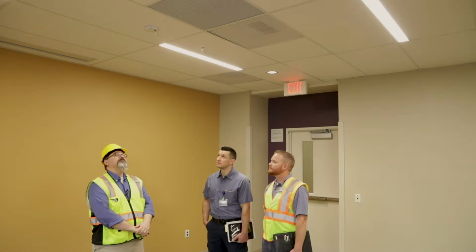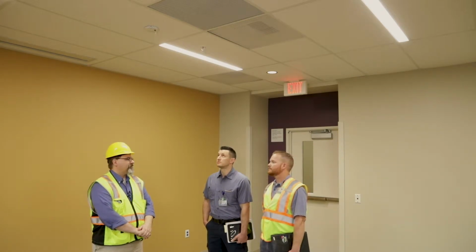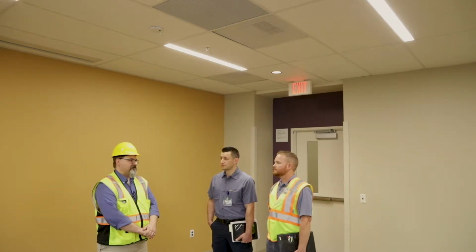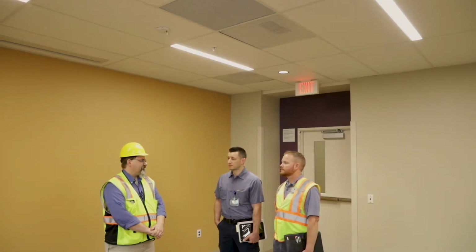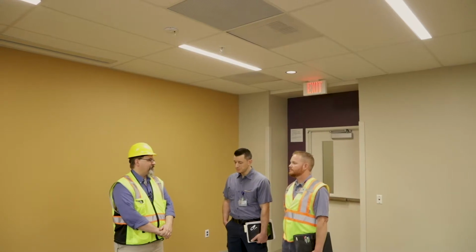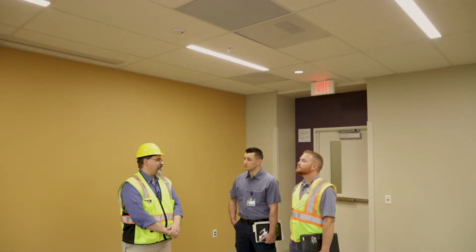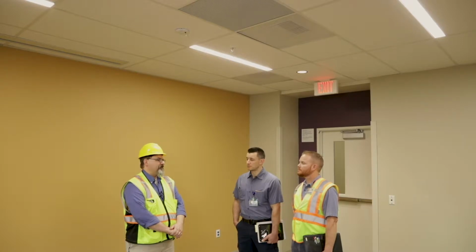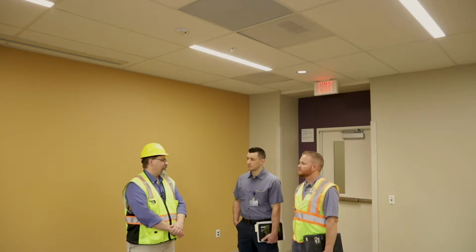So we're back to the sensors here. Most of the sensors in the building have been programmed to be manual on, so you have to go to the switch to turn your lights on. With the exception of bathrooms, we wanted those to be auto on, so when you walk into a bathroom, the light's on. If you're sitting in the bathroom and the lights go off after 20 minutes, which is the time limit, you wave your arms around, and the ultrasonic in that first 5 seconds should be enough to turn it on.